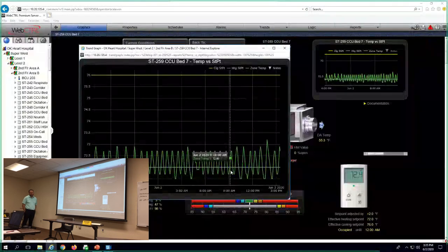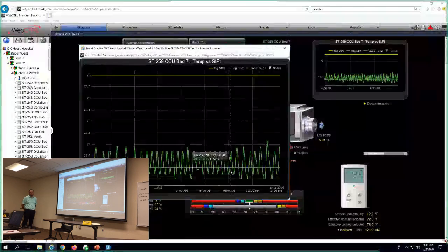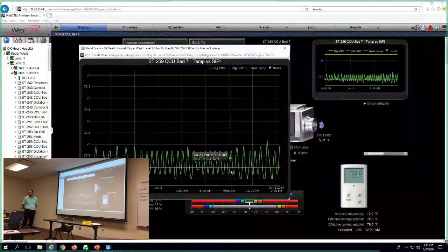Well, we can increase how far they can adjust it. That's changeable. The plus and minus 4 to 6, you can change it to 12 degrees, or 15 degrees. For patient rooms, we could tighten the deadband, leave ours at 72 and 70, give them more ability to adjust and let it lie back. I think there are ladies who want it at 80 degrees. Gosh, get it up there.